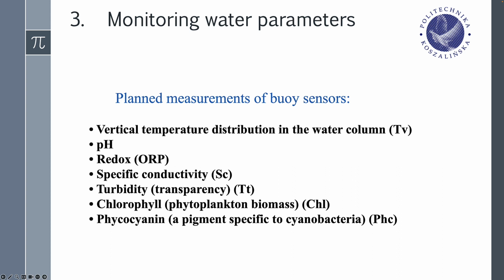Phycocyanin, a pigment specific to cyanobacteria, PHC, an important parameter in warm periods when the reservoir is used for recreational purposes. An increase in this parameter may indicate an approaching moment of cyanobacterial blooms, an early warning system. The measurement is carried out in a manner analogous to the chlorophyll measurement, using an LED-emitting light with a specific wavelength, 620 nm, and a detector, 650 nm.